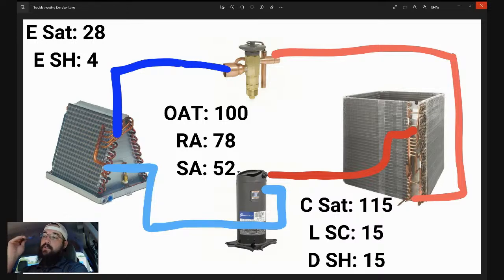Okay. That's an interesting one. Let's work through that. Improperly mounted TXV bulb. So in this particular case, the bulb cannot read the suction line properly. So what's going to happen? If you're not reading suction properly, then it's going to read the ambient air moving around it. So let's say our ambient air around the bulb is around 52 degrees. If the TXV is shooting for, let's say, a 12-degree superheat, 12 to 15, we'll use that as our example, then we're going to see the saturation increase in superheat. No, we're going to see saturation decrease, but superheat is going to increase.